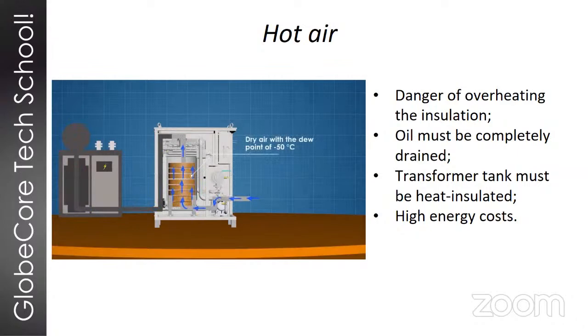So to reduce the heat loss when you do this dry air processing of the transformer, it's probably advisable to insulate the transformer tank from the outside. And also, since the tank is actually quite large, if you input air into the tank at a temperature about 100 degrees Celsius, you might have overheating there. But on the other side, the temperature will not be enough, so there will be some uneven heating. And all of this makes hot air drying less than perfect and less than most efficient. And it's usually only used when there is no other alternative.